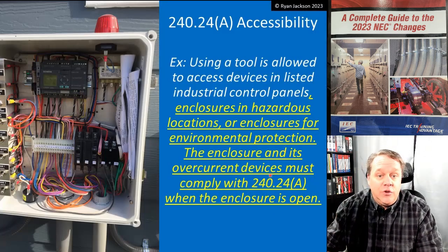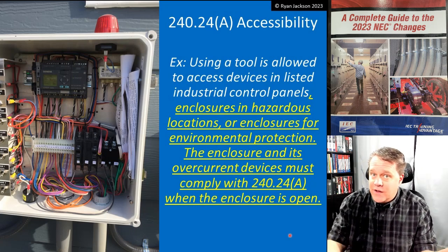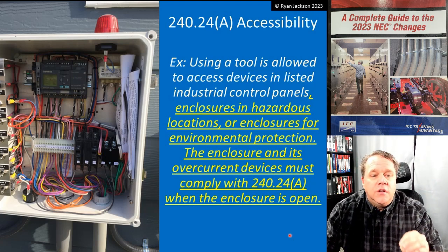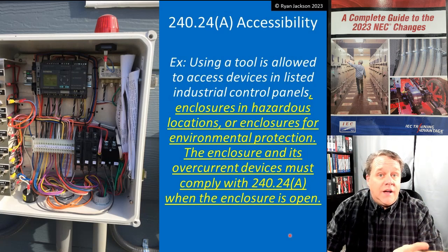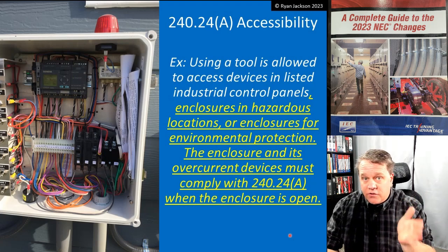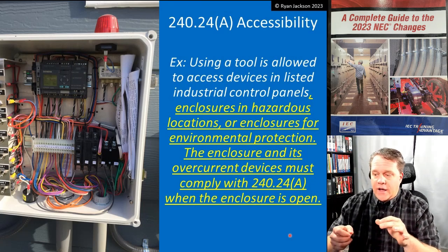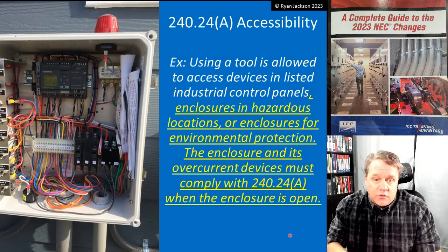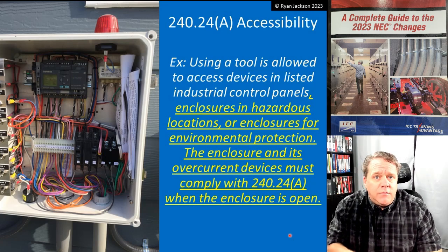There's an exception: using a tool is allowed to access devices in listed industrial control panels — a screwdriver, nut driver, ratchet — or enclosures in hazardous locations. Have you ever seen an explosion-proof panel board? You don't buy those at Home Depot. In order to get to them, you've got to unbolt everything, so yes, you're going to have to use a tool.